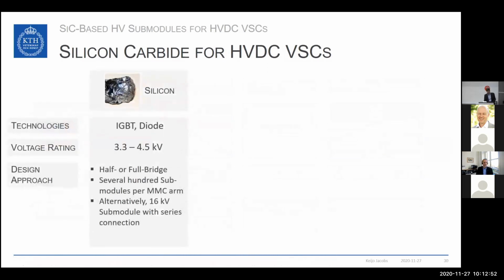For the state-of-the-art implementation, the following approach is used. We would use a silicon IGBT and a diode. Those have a voltage rating of 3.3 until 4.5 kilovolts. We would then use half or full bridge topology for the submodule and have several hundred of these submodules connected in series. Alternatively, we can series connect the silicon devices and have submodules with blocking voltages that are higher, for example, 16 kV.